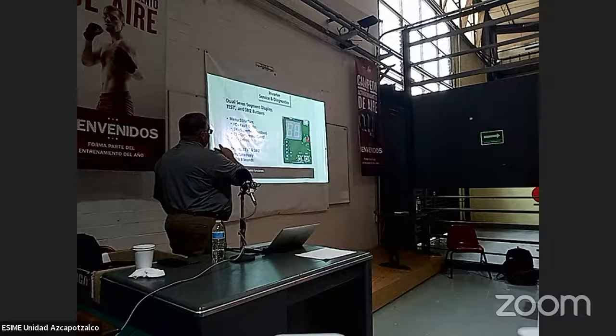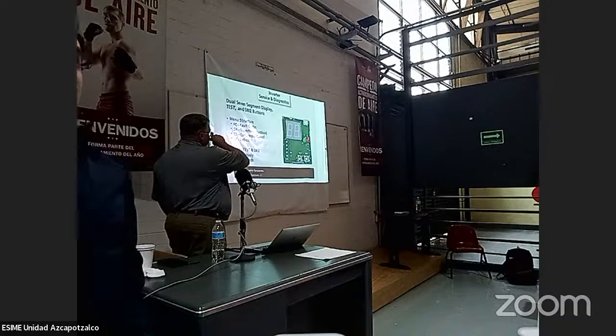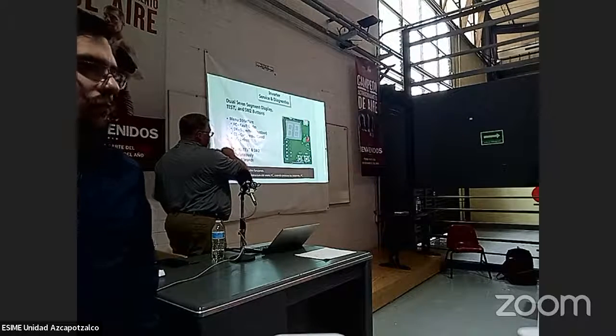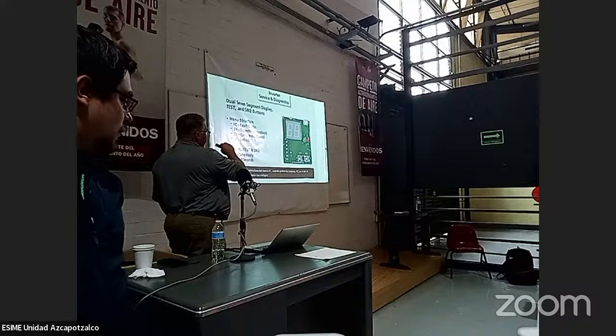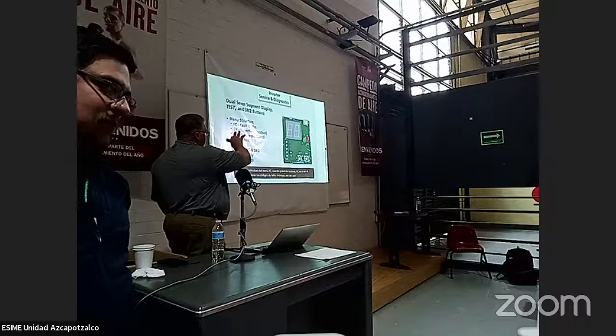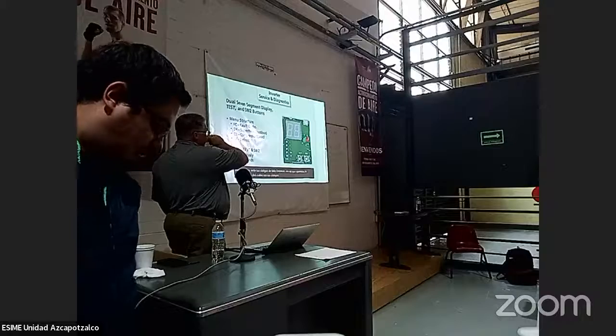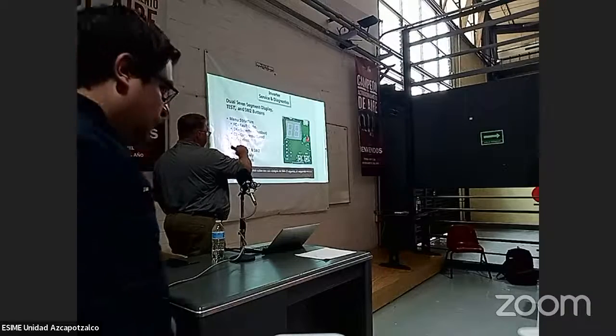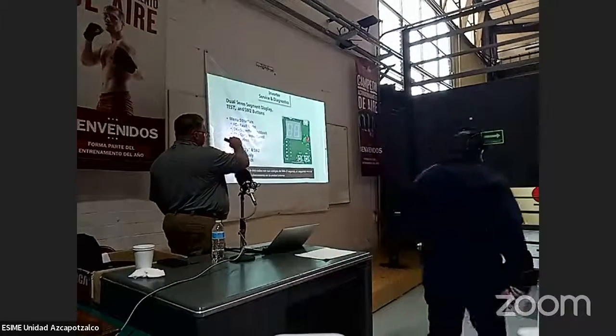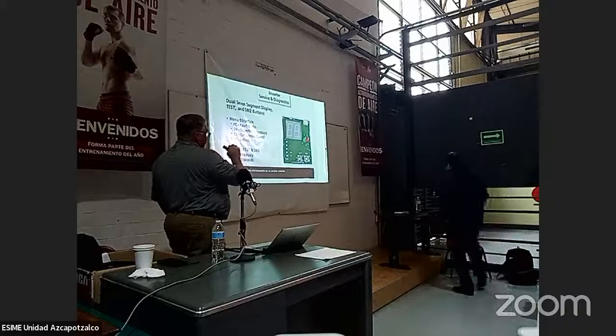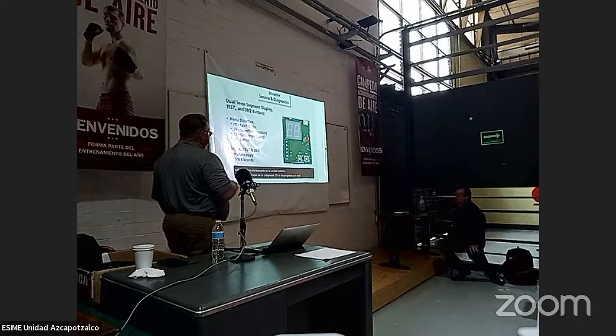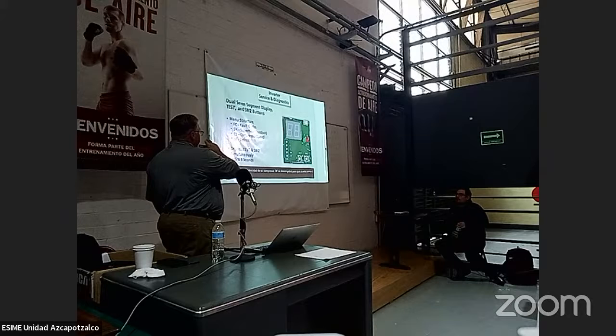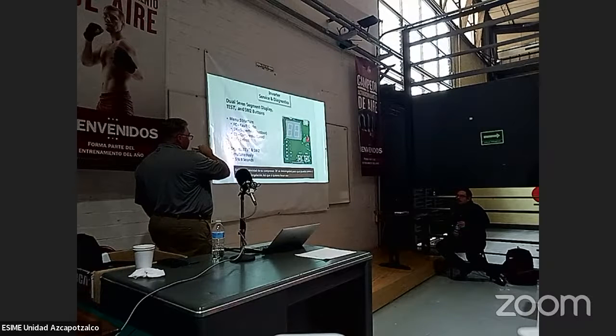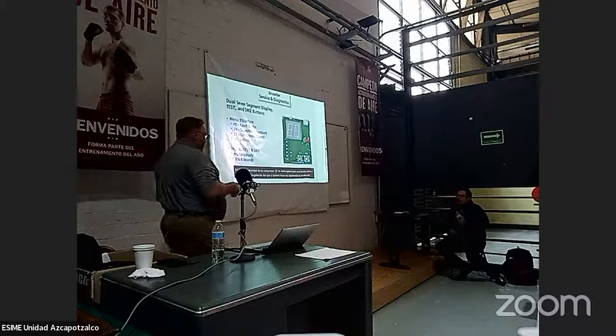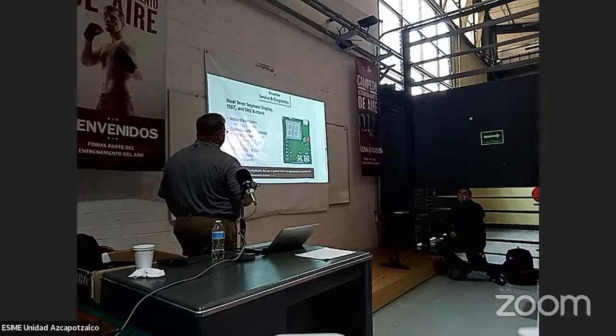So the menu structure: when you press the buttons, FC is going to be the first one, your fault codes. Once that pops up, you'll select it, and it'll tell you what your fault codes are. The second one is what your super is on the outdoor unit. The CS will be your compressor speed, DF will be defrost, so you can put the system in defrost. If you want to do that, you will press test and SW2 simultaneously for 5 to 8 seconds. You'll go into that function.